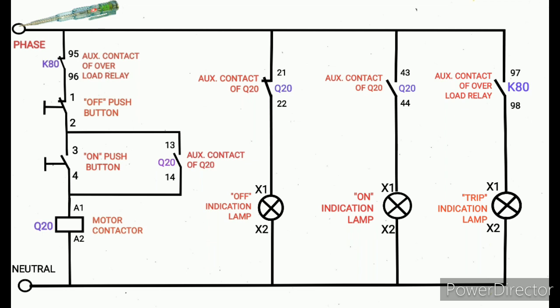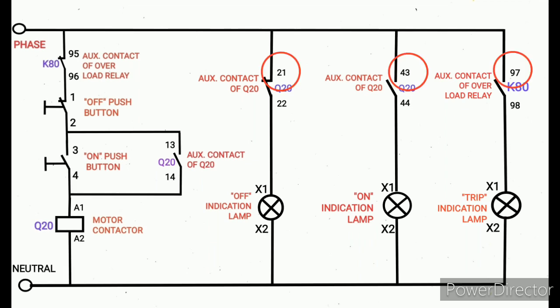After that, where the phase is going, where the phase line is looped, all the terminals we need to check. Here: auxiliary contact of Q20 21, auxiliary contact of Q20 43, and the auxiliary contact of overload relay. All the terminals we need to check. If the tester glows, the terminal's phase is okay. Otherwise, if it has any loose contact, we need to correct.